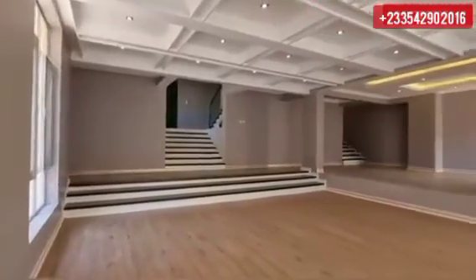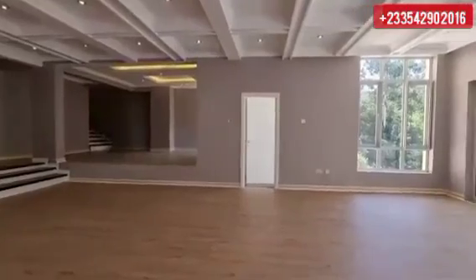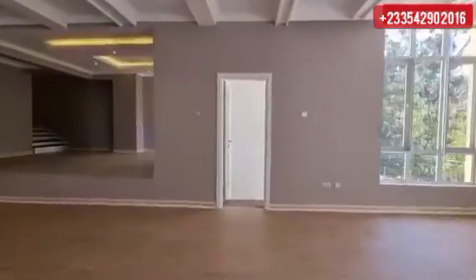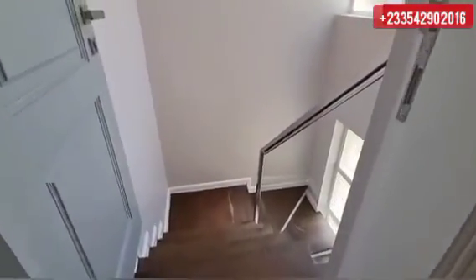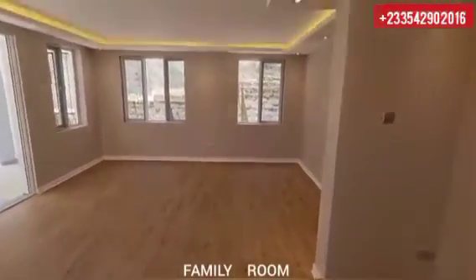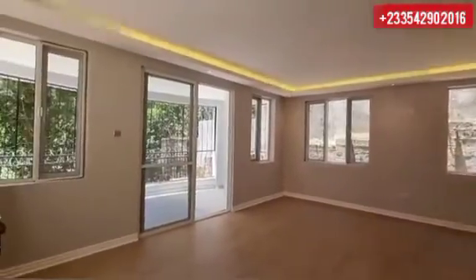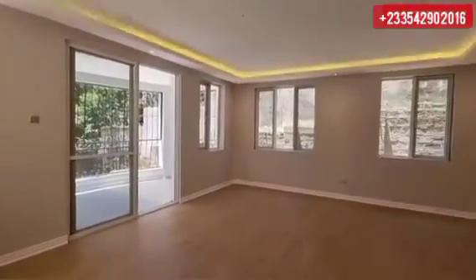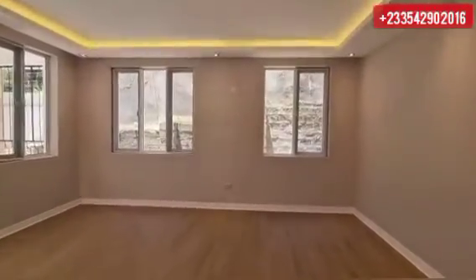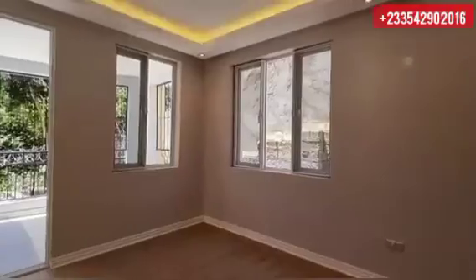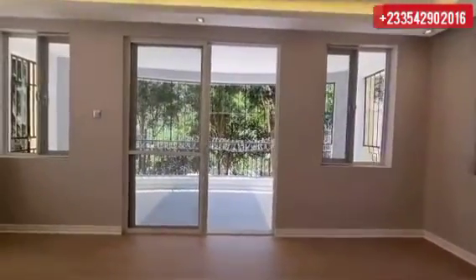Then you want to add your lighting to it. So the small power point is 11, and your AC is let me say 65. You add your small power point to the AC, and make it 76. Then you work your lighting system per meter square: 5 multiplied by 5, you got 25. Multiply 25 by 76, you got 1,900, which is 1.9 kilowatts. So that room is 1.9 kilowatts load.